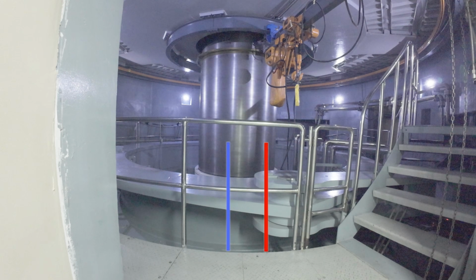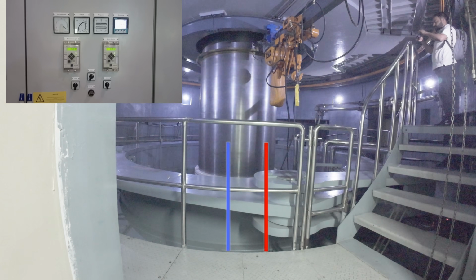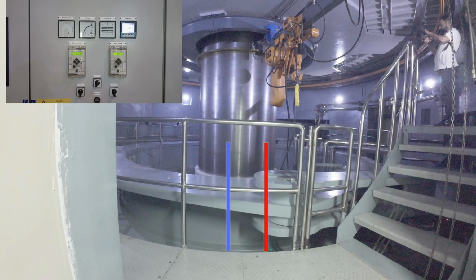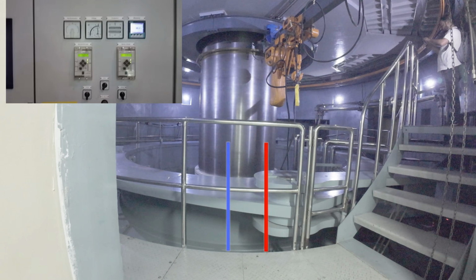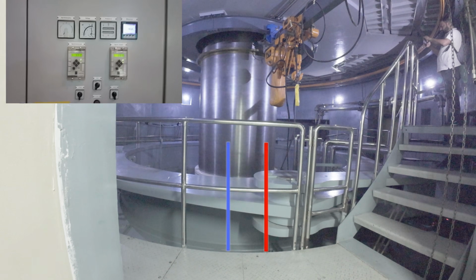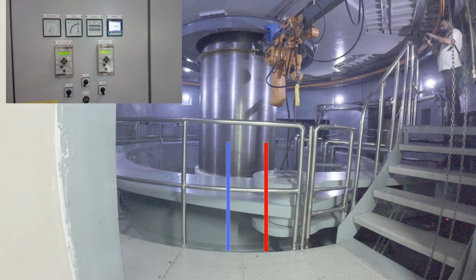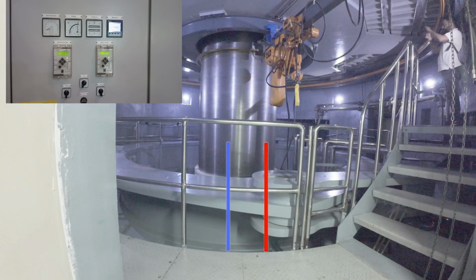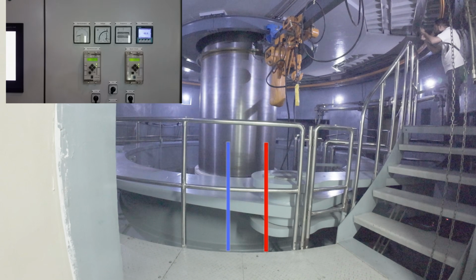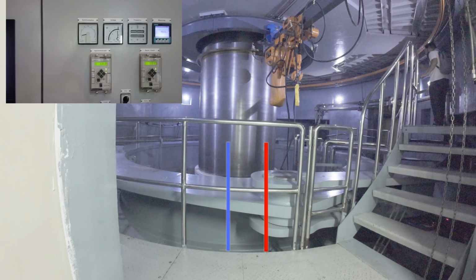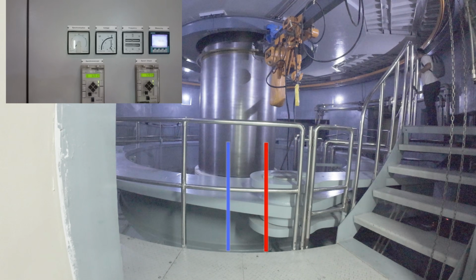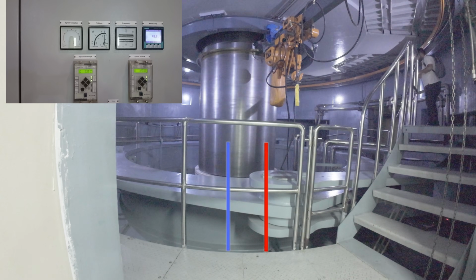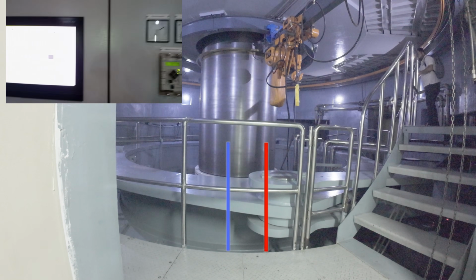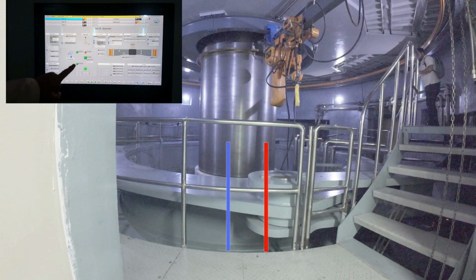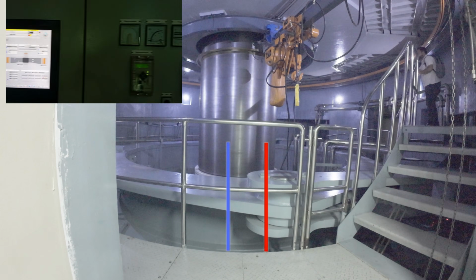Okay, before connecting, the generator must match the grid perfectly. I've told this already in many videos, and I've also made a video on the excitation system. If you want to look at it, you can check it here. Its speed, voltage, and timing must all be aligned. Imagine trying to jump onto a moving merry-go-round. If your speed doesn't match, things won't go smoothly. The electricity grid works the same way. The control system carefully adjusts the turbine until everything matches perfectly. Then the circuit breaker closes. In a fraction of a second, the generator becomes connected to the national grid. The power can now begin flowing to homes, businesses, and industries.